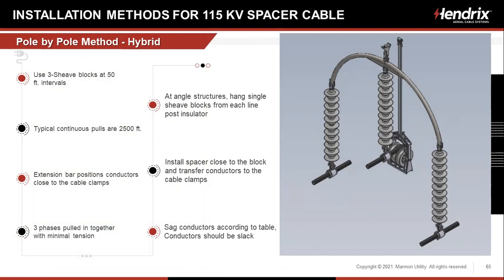Installation. Well, we're going to have a hybrid installation method. We're basically going to use the pole by pole method. We use 3-sheave blocks at 50-foot intervals. Again, so instead of having the spacers every 30 feet with 15, 25, 35, 46, and 69 kV, when we go to 115 kV, we're going to have spacers every 50 feet. So that is one obvious difference as we go to 115 kV.